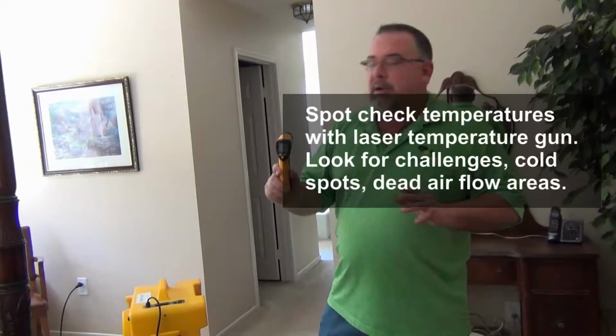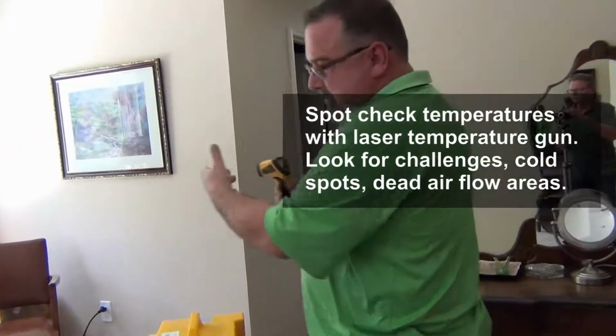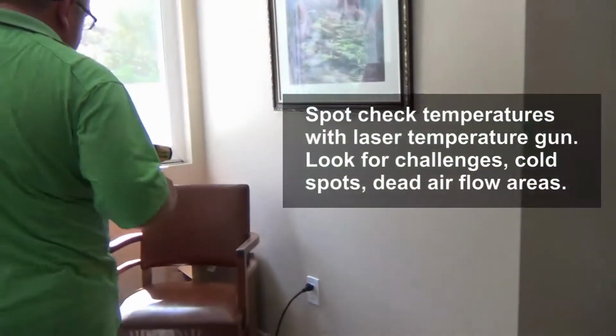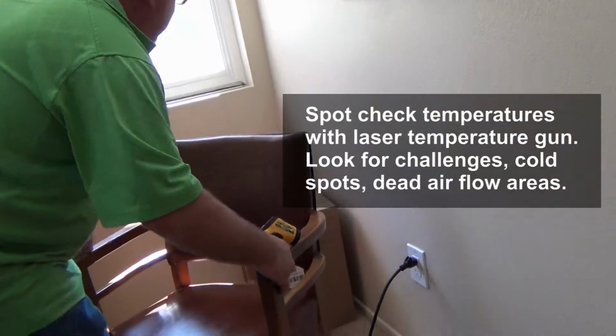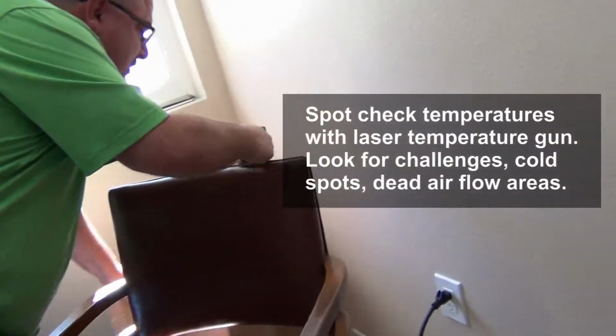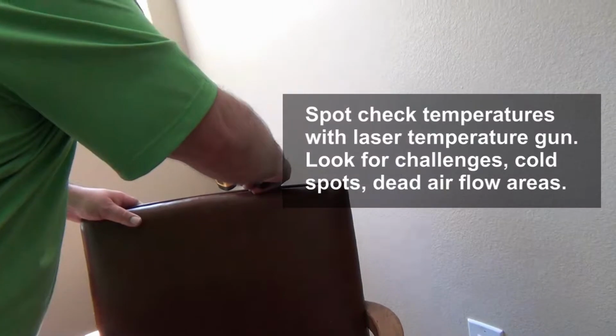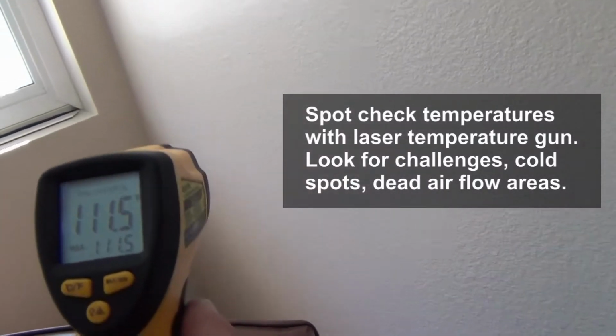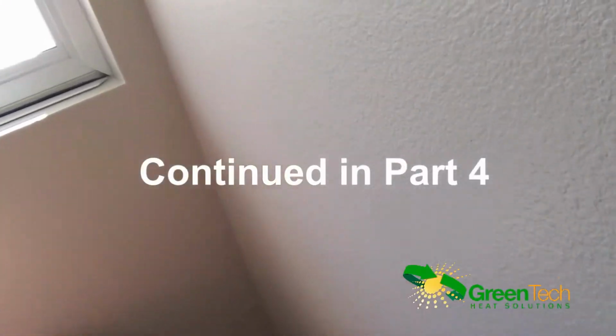A digital handheld thermometer is your best friend. What you can do is come to, say, this box sitting on the ground here. You're going to want to lift that box up and take a temperature reading underneath it. It's 111 degrees, so that tells me that's a cold spot.